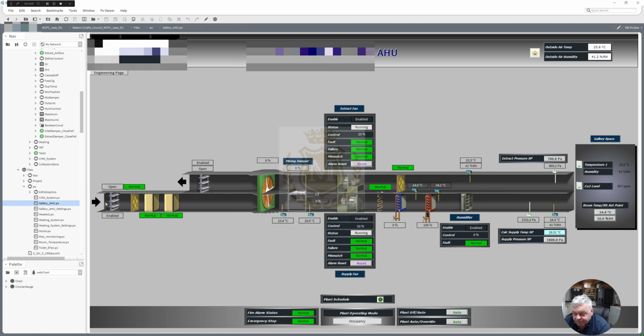We're taking air in from the outside, going through a panel filter, going through a bag filter, going through another filter as well. Bear in mind it's a gallery, so we've got to make sure we are putting clean air into this. We've got the temperature there at 23.4. We're not recirculating because that's roughly the same temperature there. We're going through that motor, pushing it through the frost coil, which is fine. There's no cooling coil on. There is a heating coil, and we are giving 24.3 degrees at this moment into the gallery.